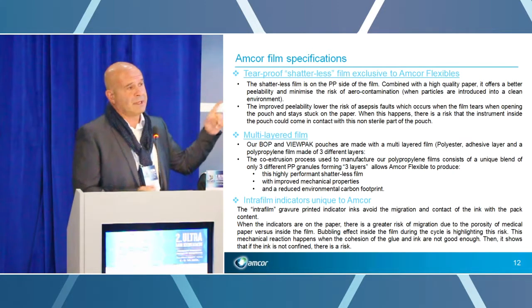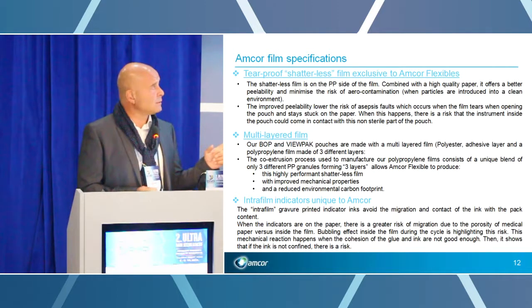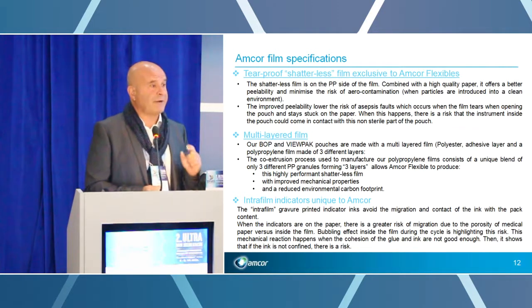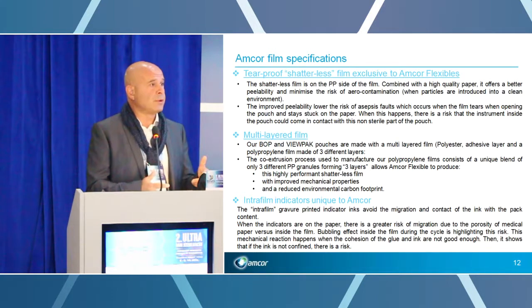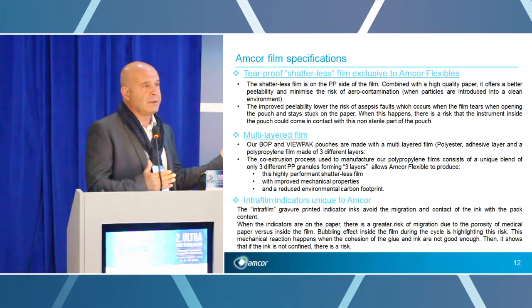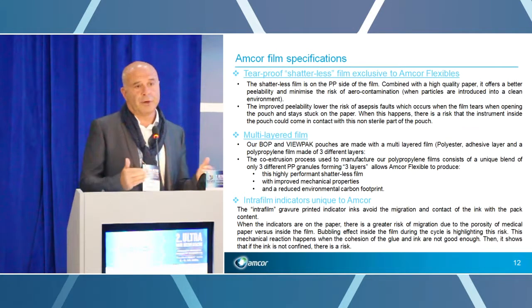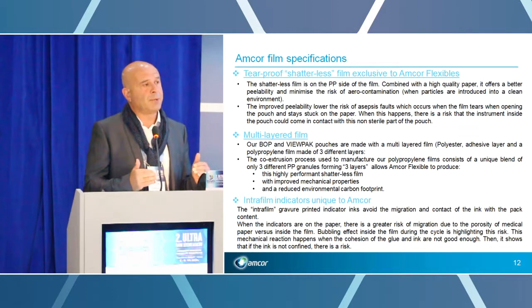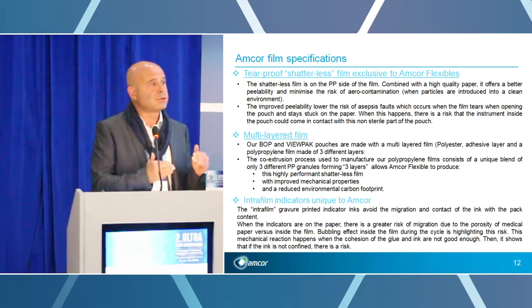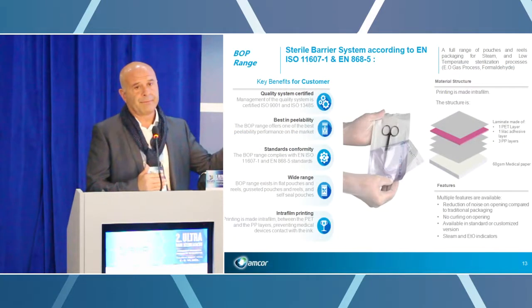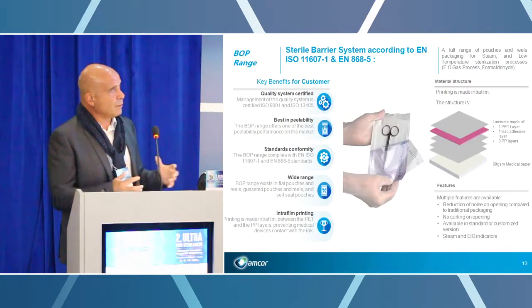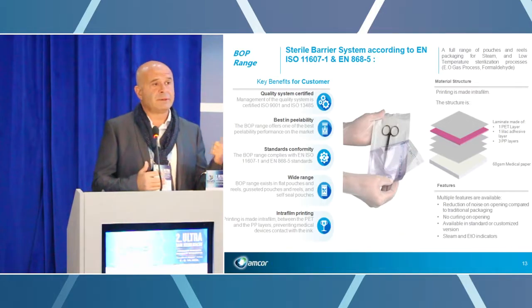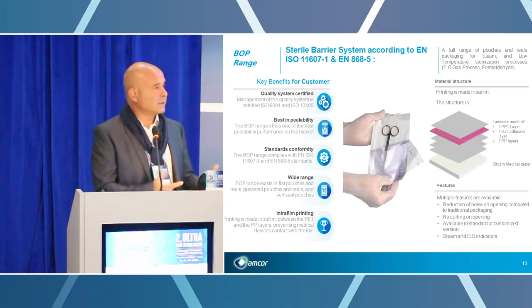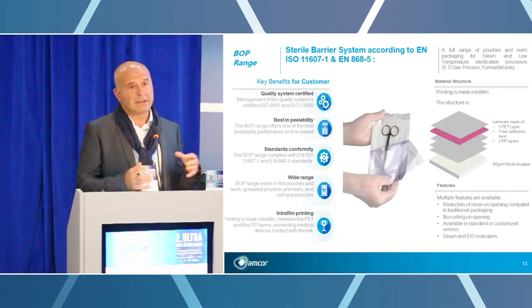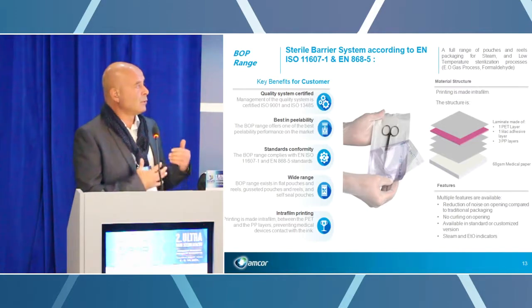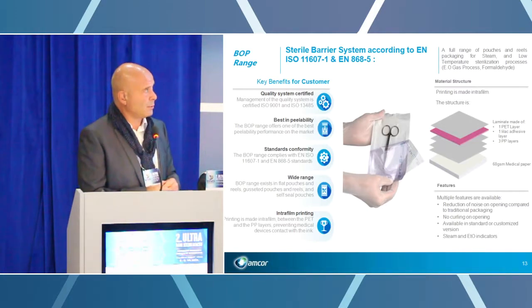Just ISO 11607 and European standard 868 part 5, because some manufacturers propose other conformity of the standard, and it's totally forbidden, because it's not for this product, it's for another product. It's very important you control just these two conformities. We have a wide range, because we have a lot of sizes, like flat or gusset pouch, and the printing inside the film. It's very important for us, because you don't have any risk of migration during the cycle.